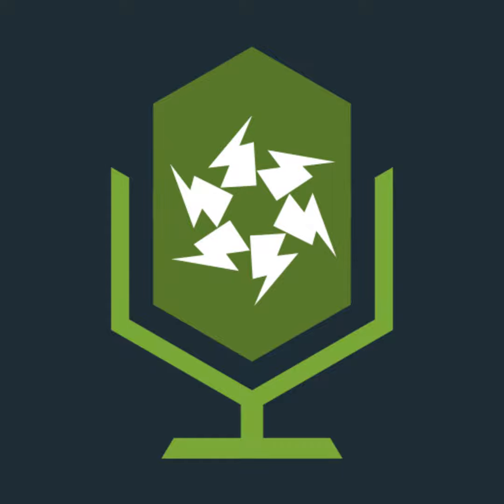This is where you'd have to work with other people. So if you're installing an electrical system, but there are other people installing, for example, assemblies or plant or distribution or even air handling units, they may not know, or you may not work with them closely enough, and it might be that you plan on having a panel put in a position, and then they decide, well, there's some gap there, we'll put a bit of equipment adjacent to that, which then inhibits the ability to freely or safely maintain it in the future.